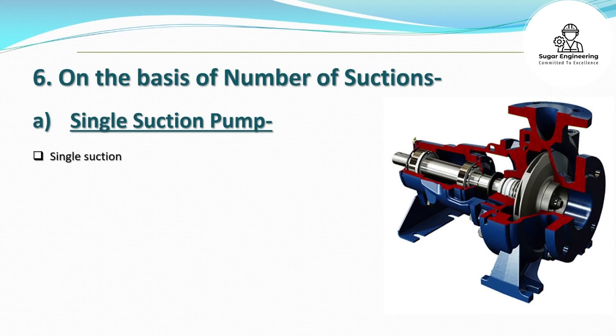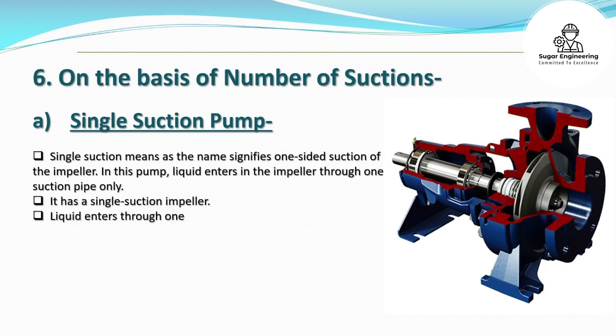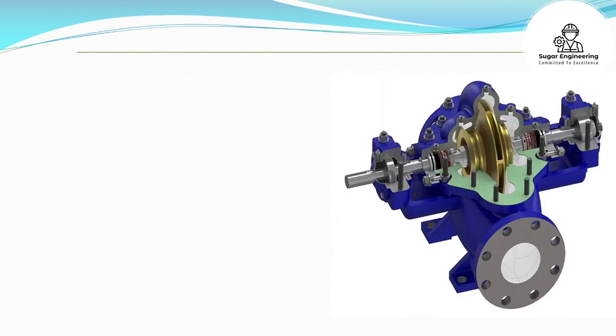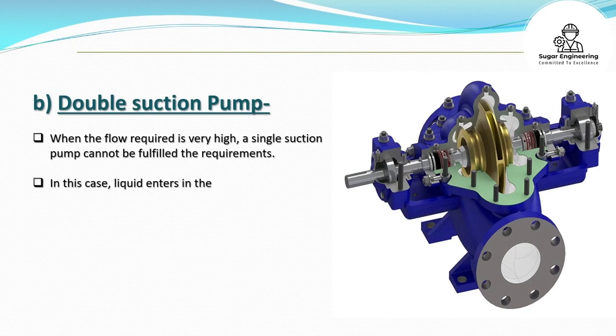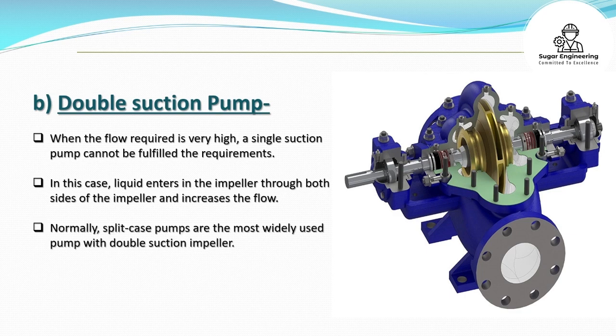On the basis of number of suctions: A. Single suction pump — single suction means one-sided suction of the impeller. Liquid enters the impeller through one suction pipe only. It has a simple design but can have higher axial thrust due to imbalance of flow coming in from only one side. B. Double suction pump — when the flow required is very high, a single suction pump cannot fulfill the requirements. In this case, liquid enters the impeller through both sides, increasing the flow. Split case pumps are the most widely used pumps with a double suction impeller.